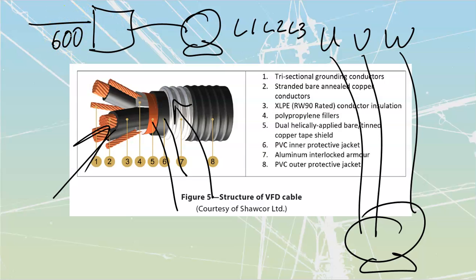Not every VFD can do this, by the way, but you are going to take 600 volts. You're going to program your motor nameplate data in there, that this is a 240 volt delta motor, and then you're going to be able to put out no more than 240 volts. Once you program that, the drive itself scales the V/F. It just says, okay, full frequency is going to be 60, and that means that instead of full voltage being at 600, this is now going to be 240, and so it's still going to maintain that proper V/F across it.